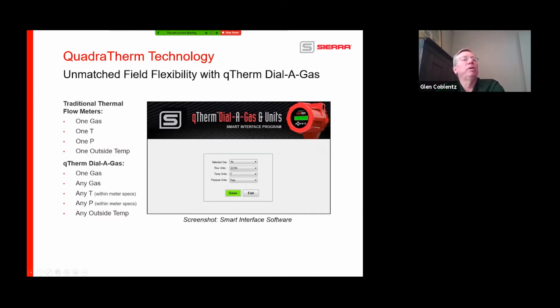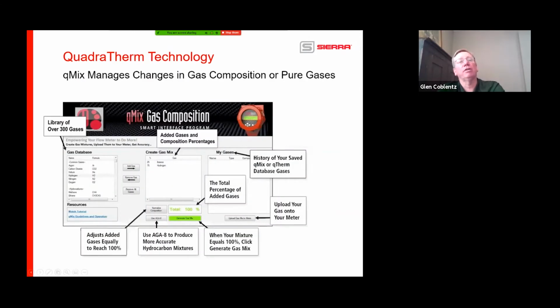Gases, T and P, temperature, it's just keeping track of everything. The SIP allows you to look at all those different things you can change in the field. One of the big things within the Smart Interface program is this Q-mix gas composition. If you see over here, every single gas under the sun is in this chart. You can use these gases to create a pure gas or a gas mixture. It can then sit in your gases database and you can upload it to the meter anytime you want.